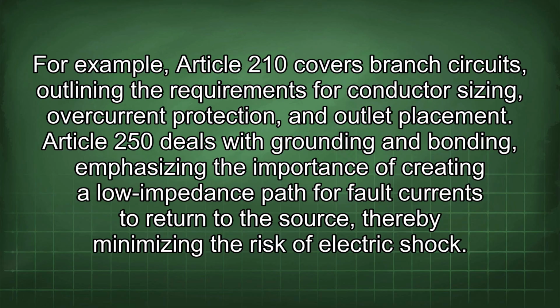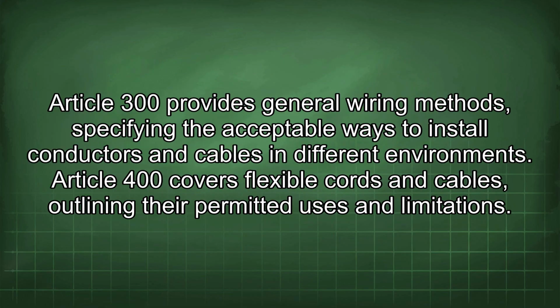For example, Article 210 covers branch circuits, outlining the requirements for conductor sizing, overcurrent protection, and outlet placement. Article 250 deals with grounding and bonding, emphasizing the importance of creating a low impedance path for fault currents to return to the source, thereby minimizing the risk of electric shock. Article 300 provides general wiring methods, specifying the acceptable ways to install conductors and cables in different environments. Article 400 covers flexible cords and cables, outlining their permitted uses and limitations.